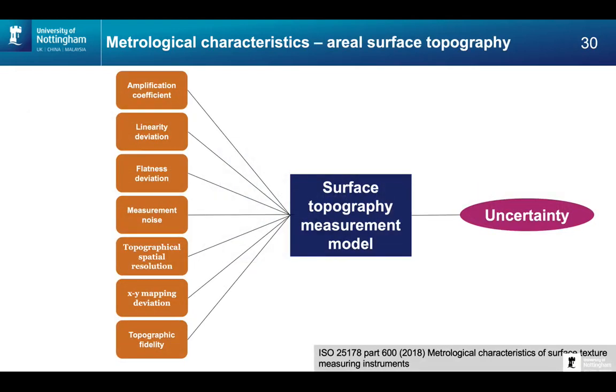These are defined, and here they are. These are defined for any instrument type, from contact systems to optical systems, and we're even applying them now to X-ray systems for extracting surfaces from X-ray systems. So here they are: the amplification coefficient, the linearity deviation. That with the XY mapping gives you the scales of the instrument, so how it operates in X, Y, Z, and the relationship between those. The flatness deviation, so the reference plane, the measurement noise. Now that's measurement noise, which means it's the noise that you will get when the object is there. It's not the noise of the instrument with no object. So that is an object dependent term.